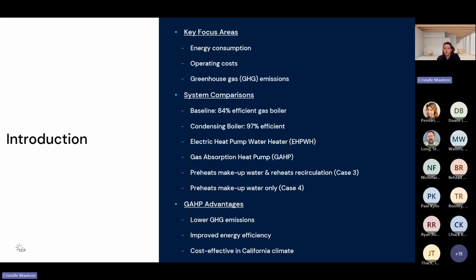In this project, we evaluated the performance of various domestic hot water systems used in multifamily buildings across California. We started with a baseline system that was an 84% efficient gas-fired boiler with a storage tank. From there, we compared it to a more efficient condensing boiler with a storage tank, then to an electric heat pump water heater, and then to two different configurations of gas absorption heat pumps.